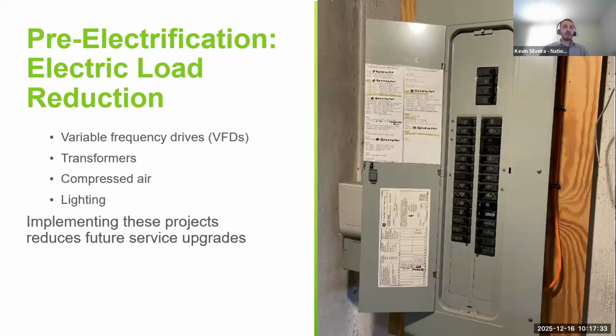So other pre-electrification projects are just reducing that electrical load as much as possible, be it VFDs, transformers, removing compressed air systems, or updating lighting. All projects that reduce that load free up capacity for those heat pumps. So if you're able to reduce your electrical consumption to the point where a service upgrade might not be needed, it makes the project much quicker to implement and you don't need costly electrical upgrades.